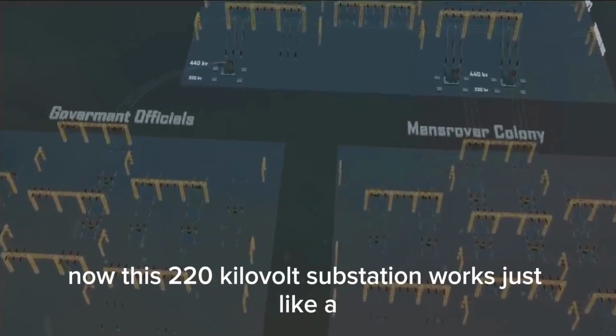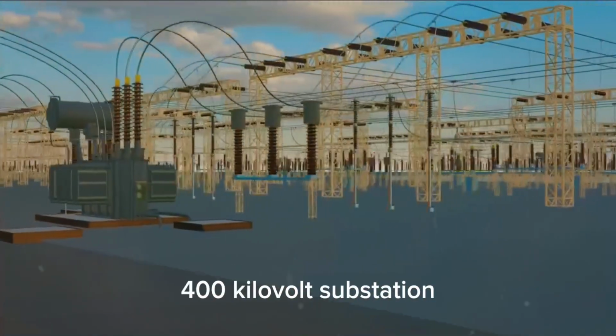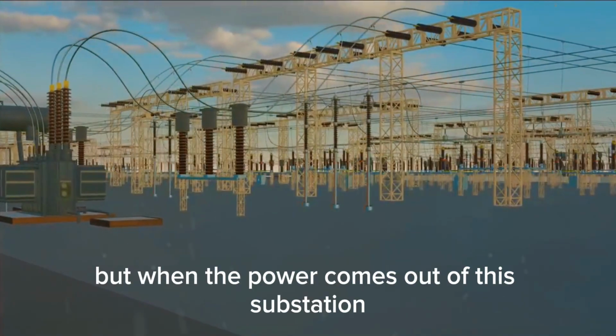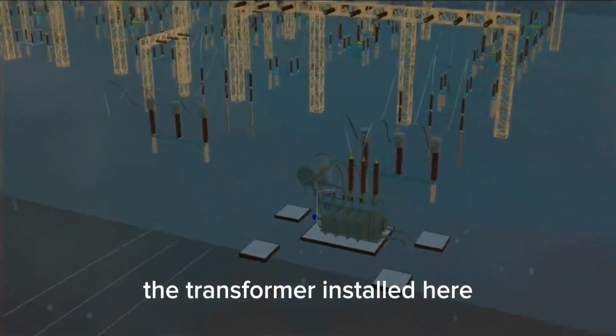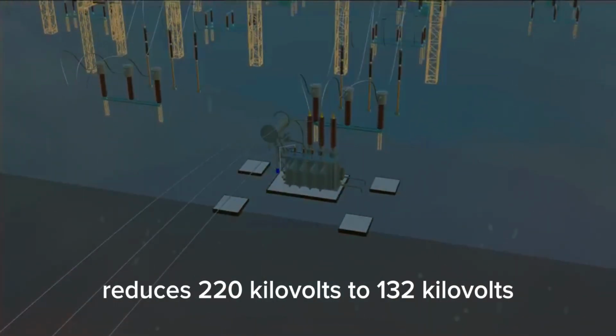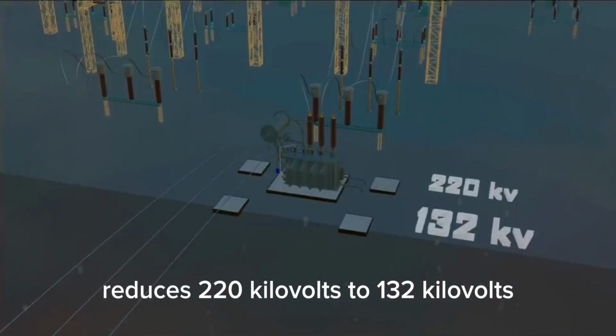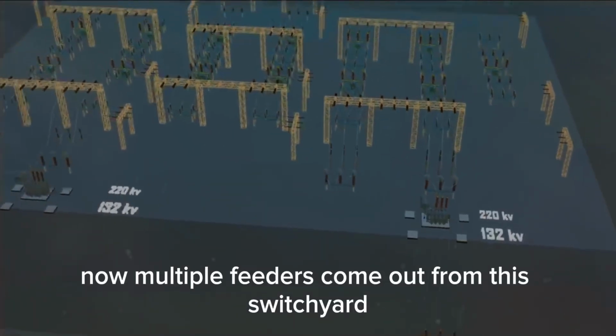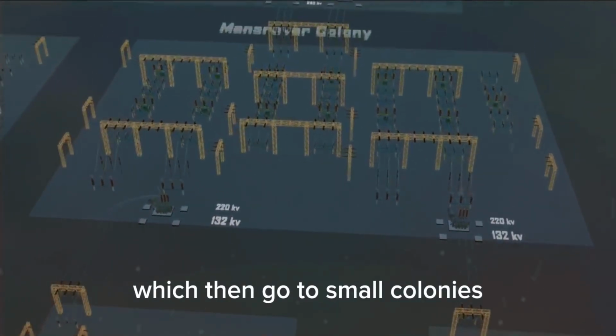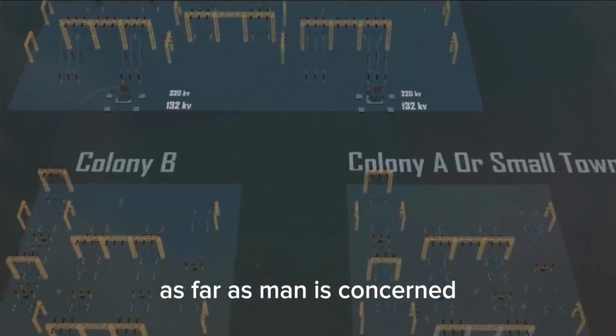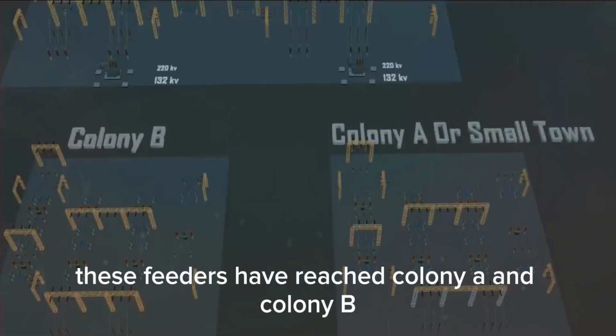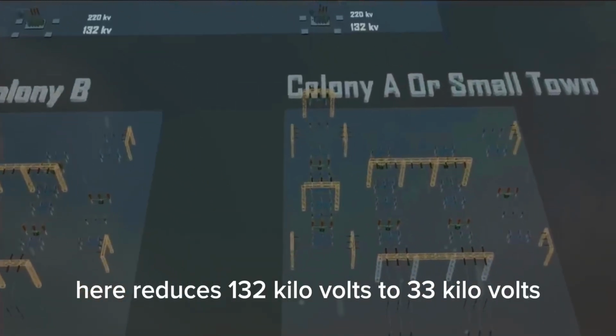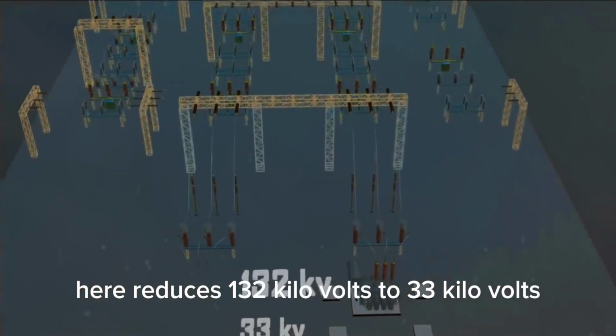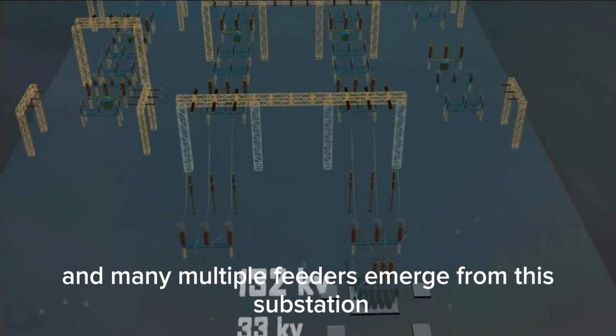Now this 220 kV substation works just like a 400 kV substation. But when the power comes out of this substation, the transformer installed here reduces 220 kV to 132 kV. Now multiple feeders come out from this switchyard which then go to small colonies. As far as man is concerned, these feeders have reached colony A and colony B. Now the substation here reduces 132 kV to 33 kV, and many multiple feeders emerge from this substation.